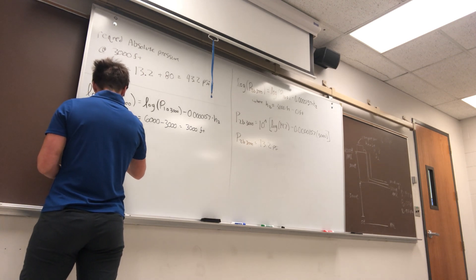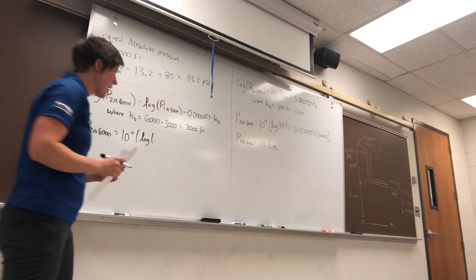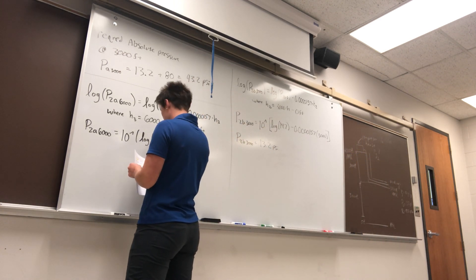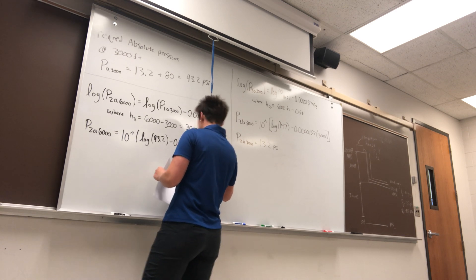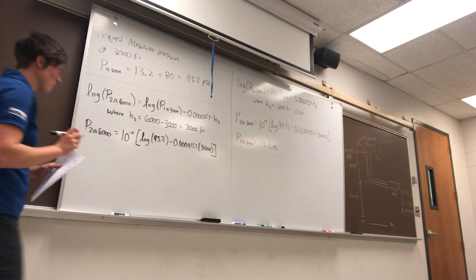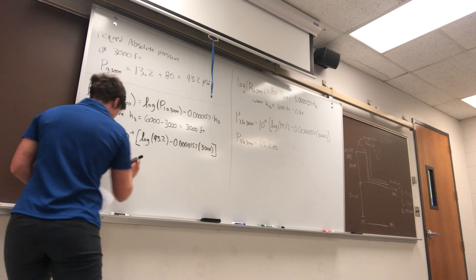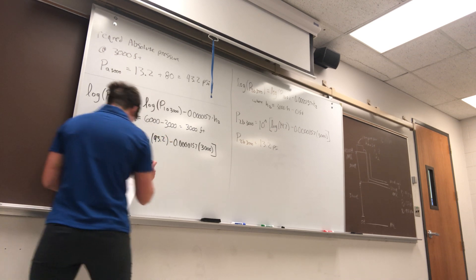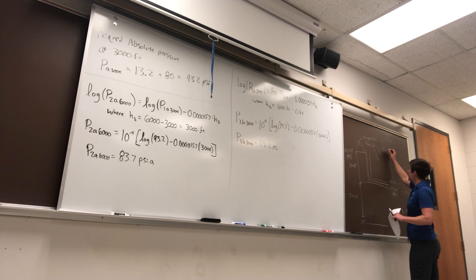Pressure two absolute at the 6,000 level equals 10 to the power of log of 93.2 minus 0.0000157 times 3,000. So far so good? Good. If we solve that, we get 83.7 PSI absolute. So we've got pressure absolute up top at 83.7 PSIA.